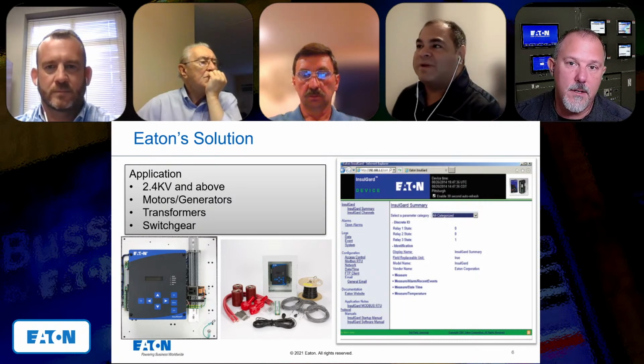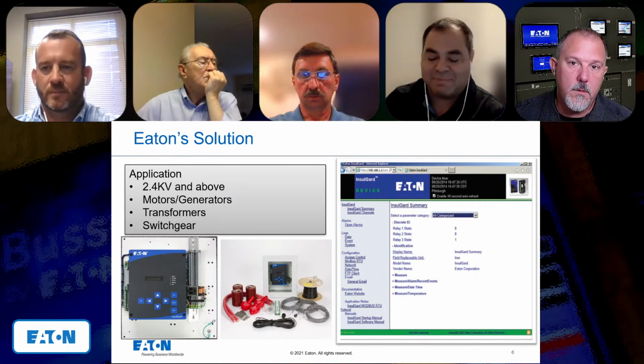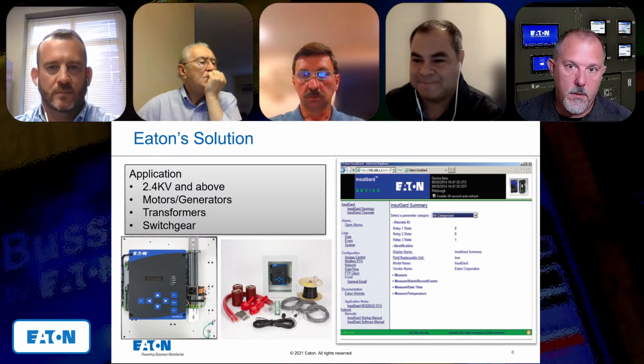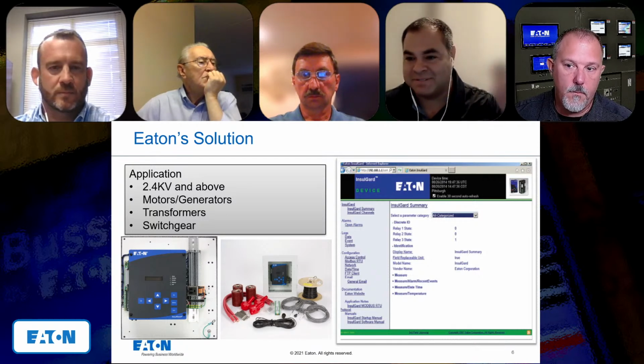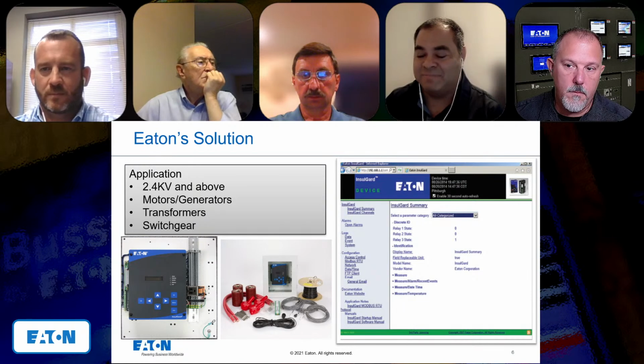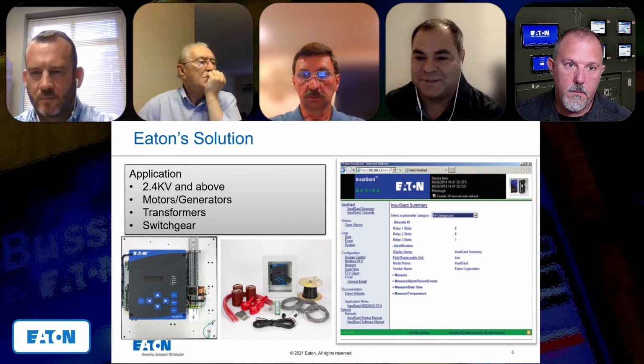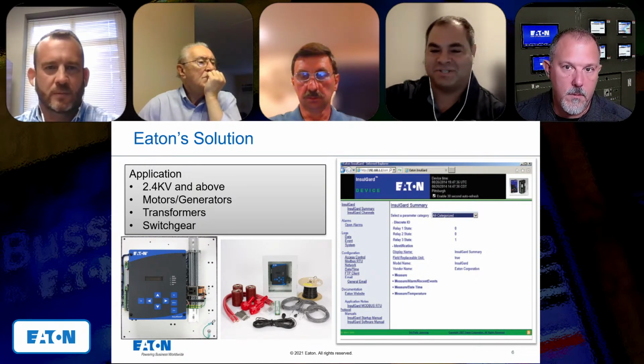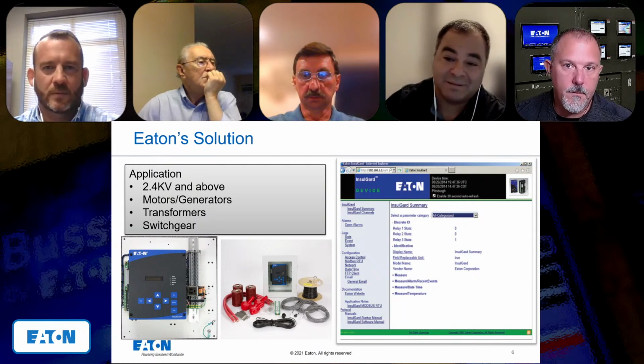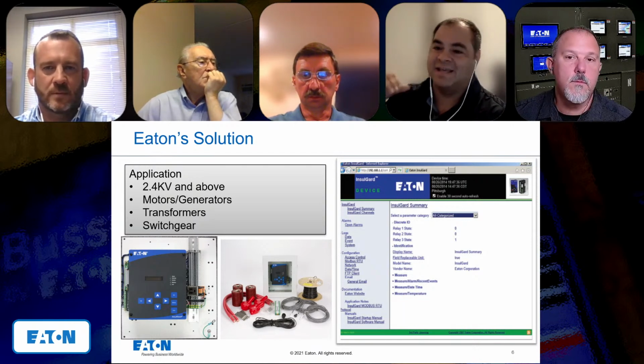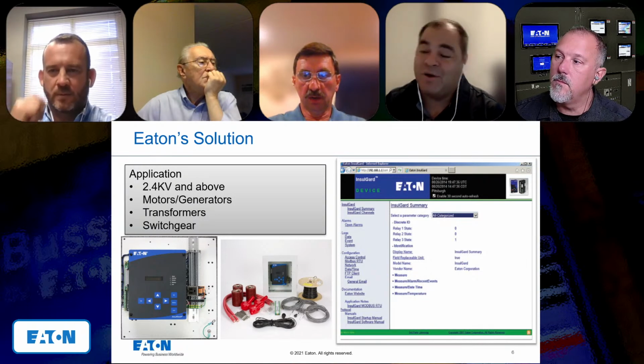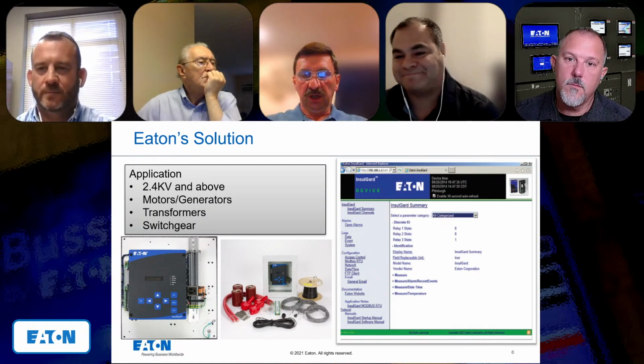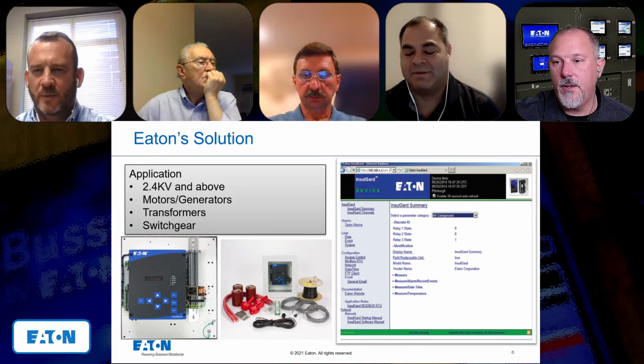One very common case is when the space heaters inside sometimes trip the breaker and nobody knows. You can detect that with partial discharge, because you'll see the partial discharge increasing at noon, for example, when the sun hits and stuff like that. Then the customer realizes that's what tripped the breaker. Interesting, it really works.